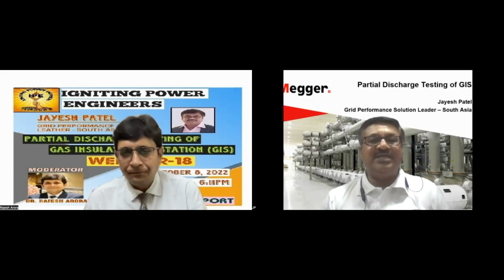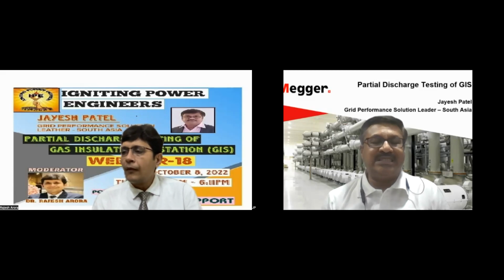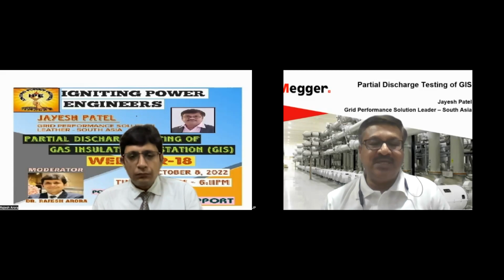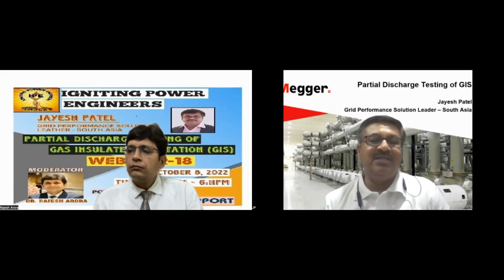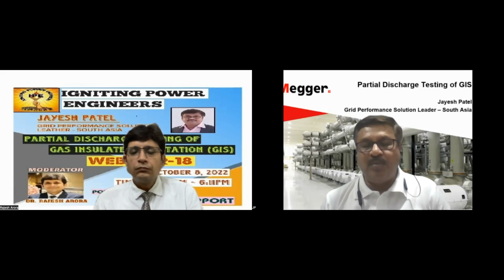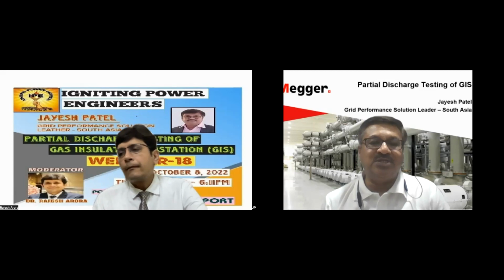Yeah, see, imperfection is in 2 cases. First is the voids, which are a part of manufacturing process imperfection and which can never be taken out of GIS. They will be there. So they will be exposed first during the HV commissioning test. So you have to really understand whether this is acceptable. If it is very minor, you can take a call along with the manufacturer whether to accept or whether you want to replace. They would probably be mainly in the barrier insulators or spacers because it's a hard manufactured product.